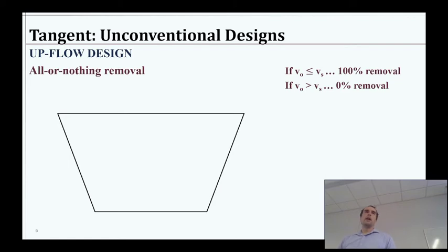There's another interesting treatment design here. It's called the upflow design. Probably won't really do too much with this, but essentially you have water flowing upwards and then it's harvested over the edges of a system like this. And it's probably circular. It's definitely this trapezoidal sort of shape, so I guess that would be conical. It does that so that as your water nears the top, it slows down. So your velocity here at the top is slower than what's coming in at the bottom.